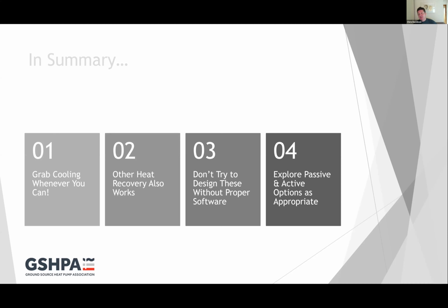Yeah, it's interesting. I'll not talk specifically about the coaxial one, but all what I'd call miracle loops. There are some very clever designs that give you very high thermal transfers around a borehole, be it coaxial, multi-probe heat exchangers, innovative materials, everything else. But fundamentally, they will not give you what the ground will not give it. If you're not designing them for the ground conditions, you might think you get a very high thermal transfer, and you will be getting that around the coaxial heat exchanger itself. But if the ground won't give it to you, you can't take it out.